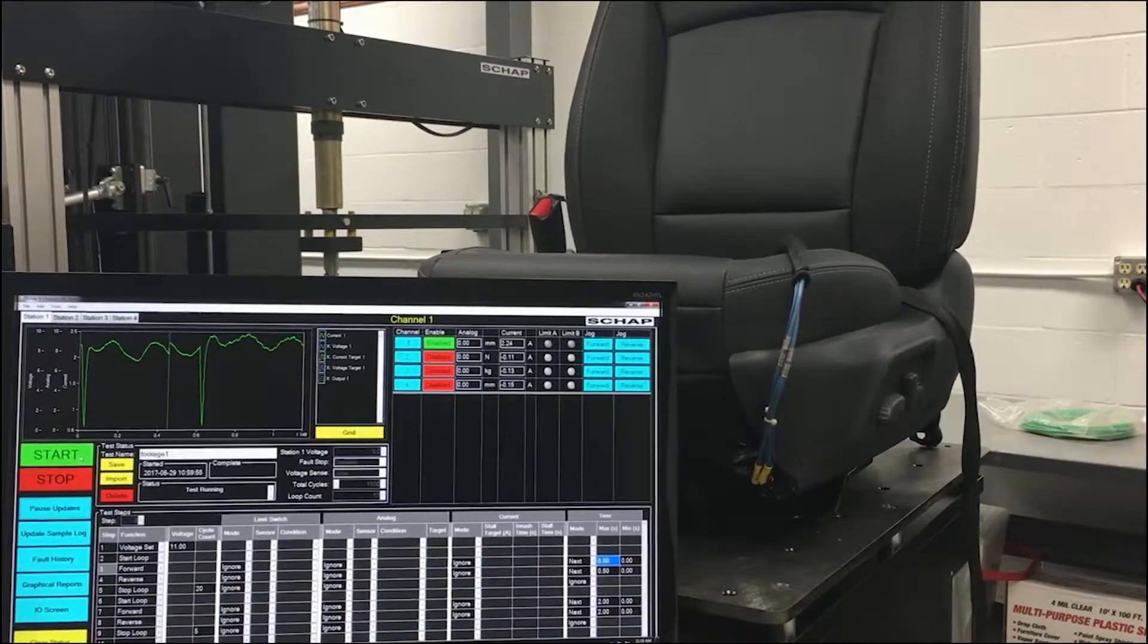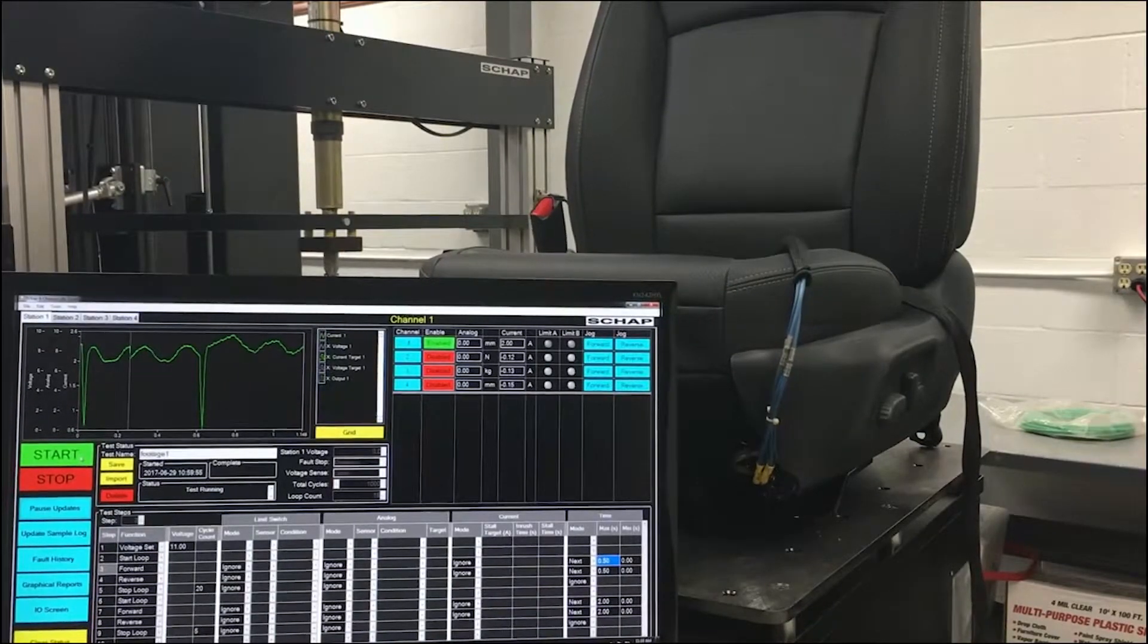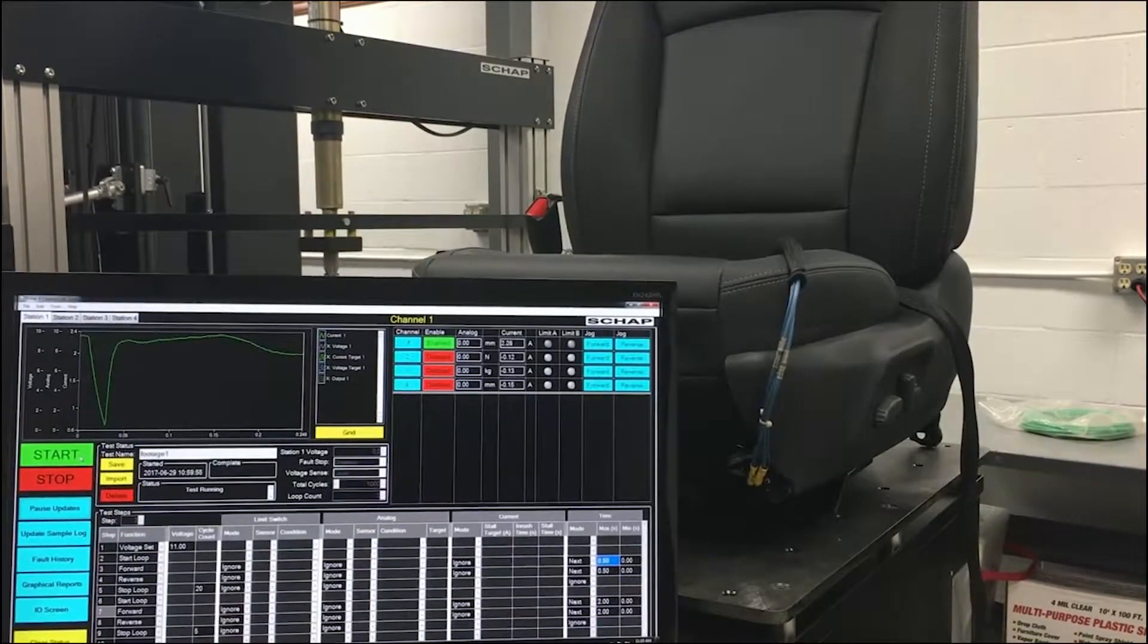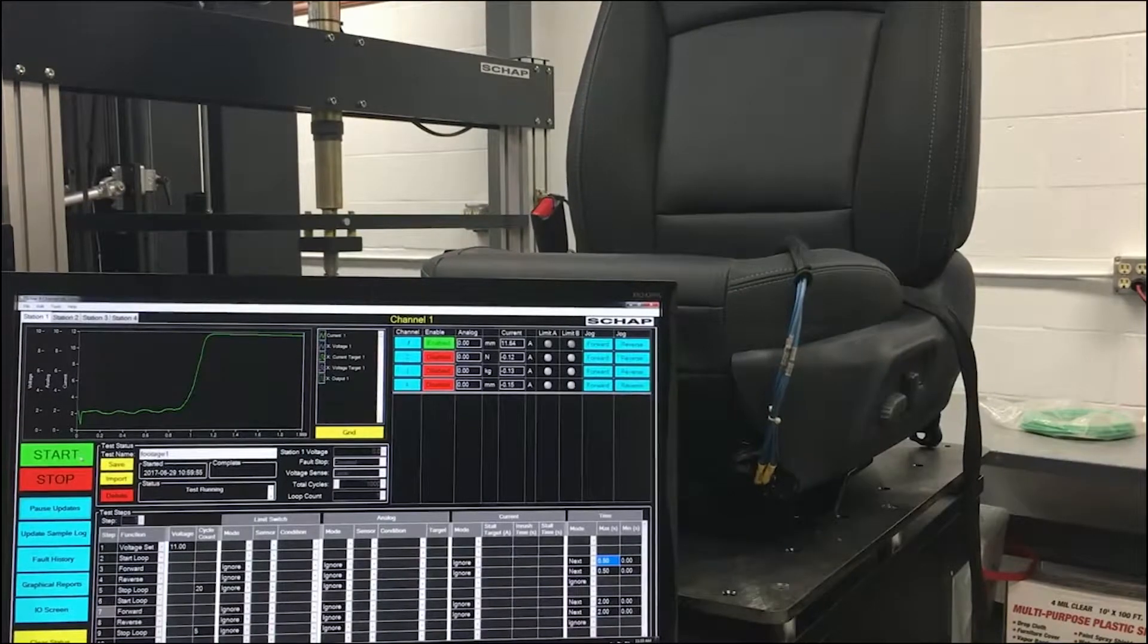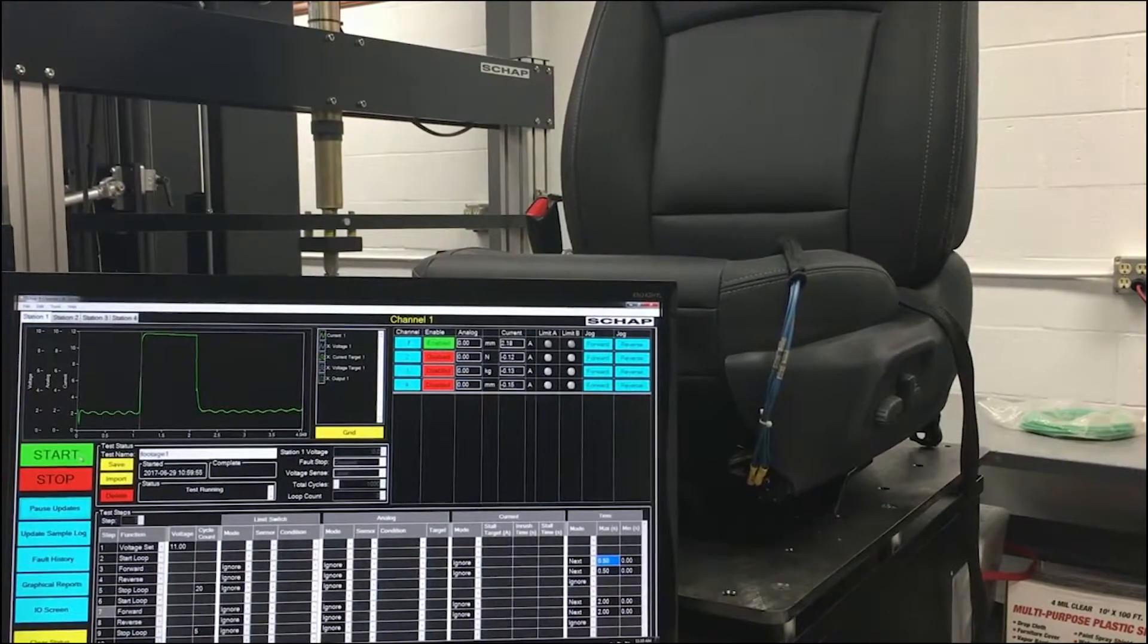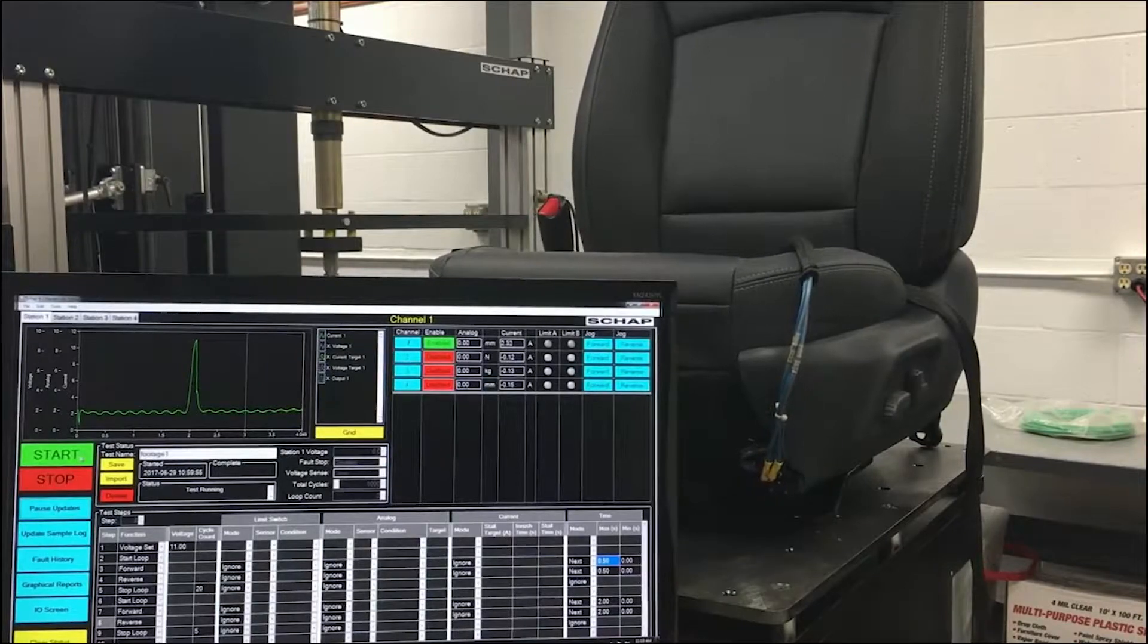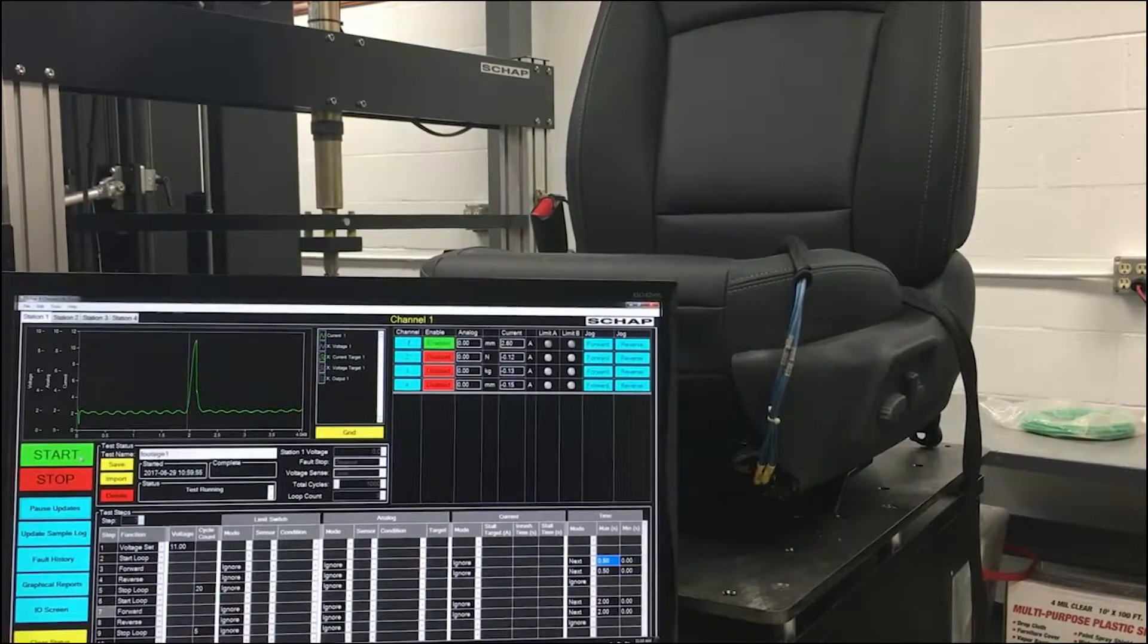The inrush time: when the motor begins moving, there may be a large spike of inrush current. The inrush time sets the duration in seconds during which the motor should ignore any spikes in current over the stall target.